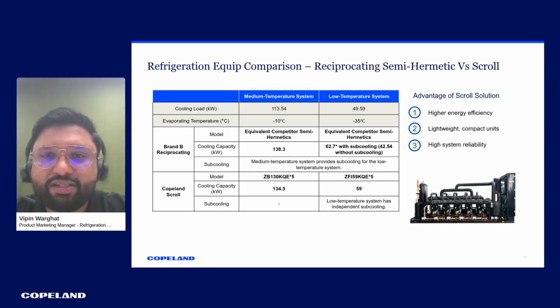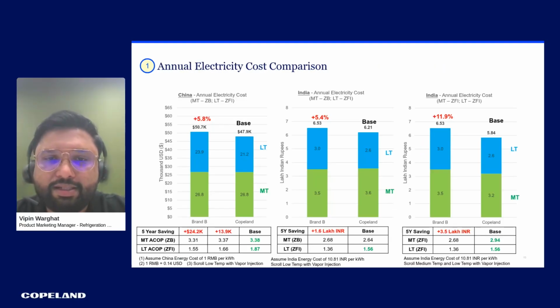Yeah. So you see here on the screen, they were using a semi-hermetic system for medium temp, which is around 140 kilowatts of capacity, and low temperature around 60 to 65 kilowatts of capacity, which was then replaced by the medium temp scroll as well as low temp scroll, which is ZB and ZFI, for equivalent capacities. And the advantage that you'll see in the coming slide is the high efficiency, the savings in space, as well as reliability. So if we move on to the next one, right? So here let's go from left to right.